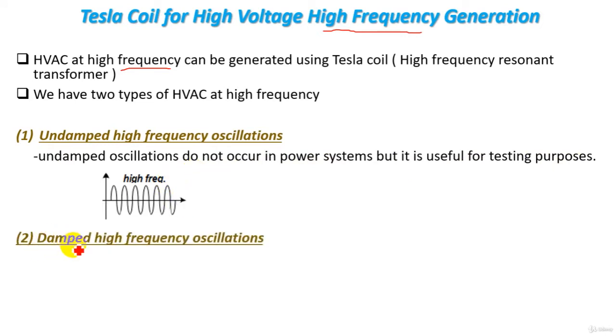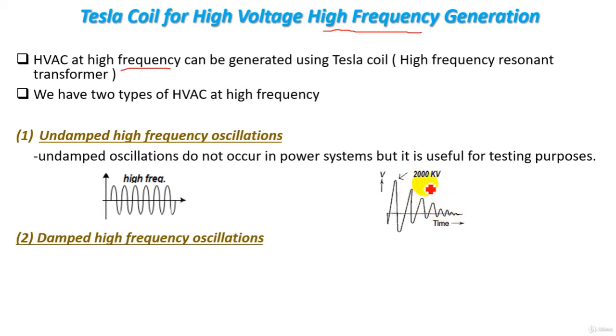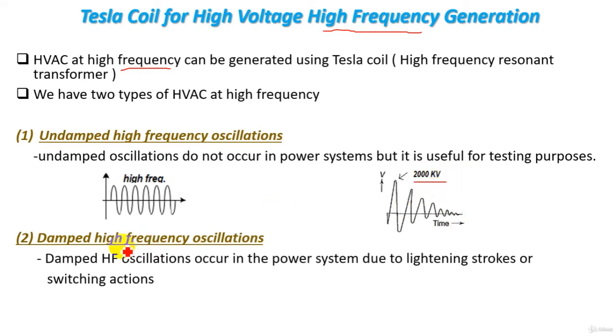The second type is damped high frequency oscillations. The waveform of this type shows damping in the oscillations, with high frequency and a peak voltage that may reach 2000 kilovolts. Damped high frequency oscillations occur in power systems due to lightning strokes or switching actions.